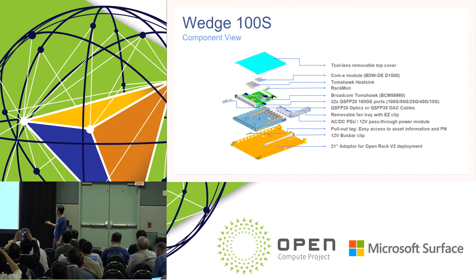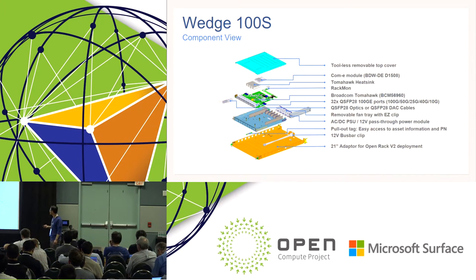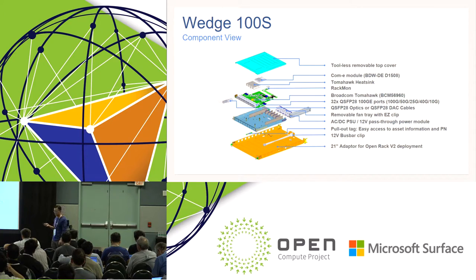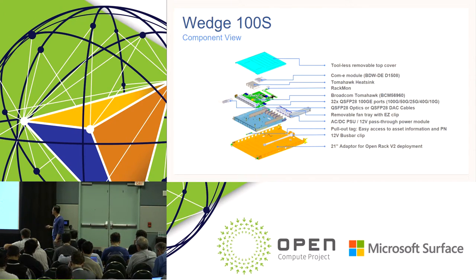This is a nice exploded view of Wedge 100S. At the bottom is the 21-inch adapter for open rack. There are two PCBs inside the box: one switch mainboard and one rack mount and fan control board. All major components are on the main switchboard. The big heat sink of Tomahawk is easy to spot. Early in our design cycle we worried about cooling Tomahawk, but it turns out it's equally challenging to cool the optics when all 32 ports are populated with 3.5-watt modules.